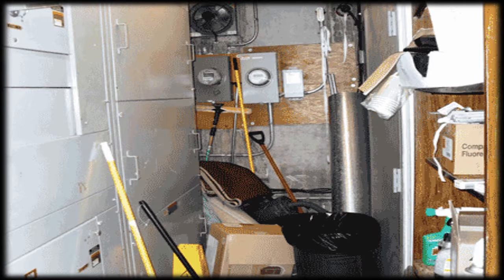Notice our spacing here. There's all kinds of stuff going on in this picture, but some of the more questionable areas would be towards the back of this room. Now again, looking at this, I'm sure that most of these things that are in this room were added after any kind of inspection. However, that doesn't change the fact that we do have potentially dangerous situations here with those meters in the back.